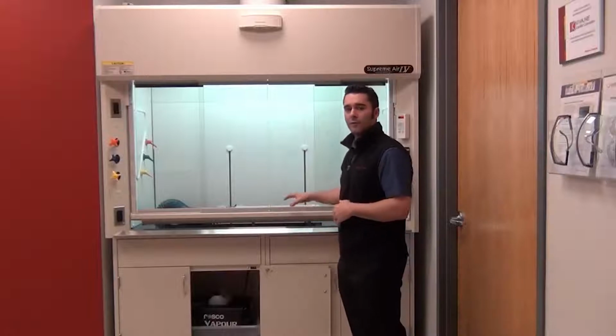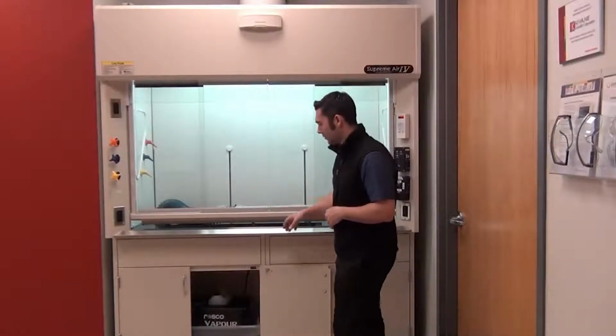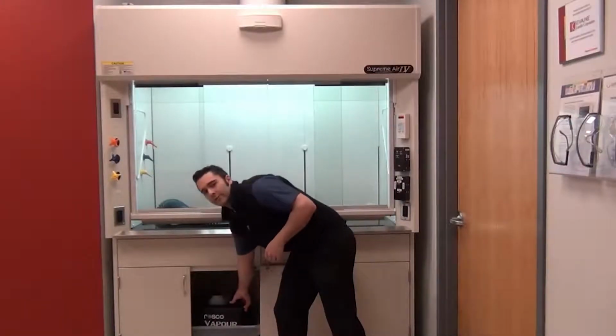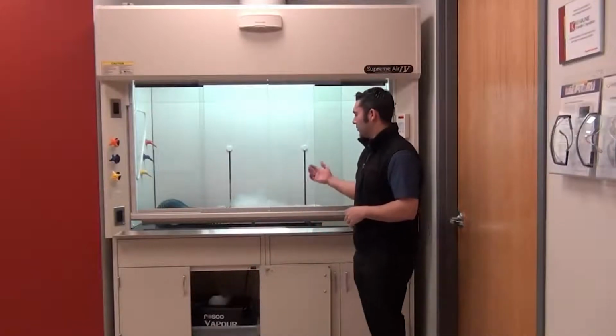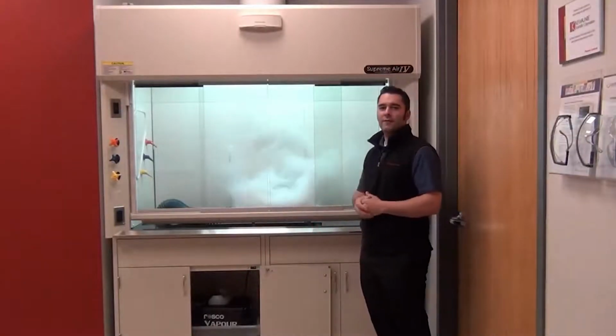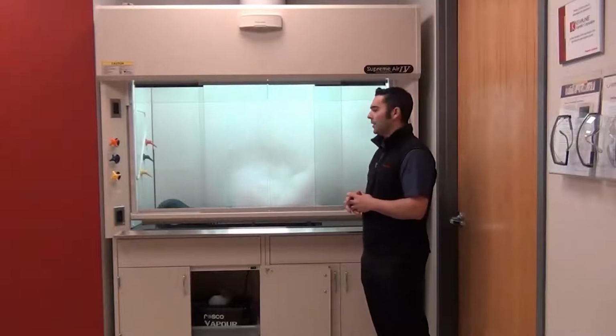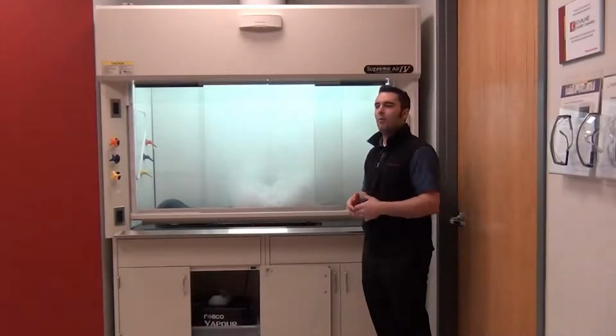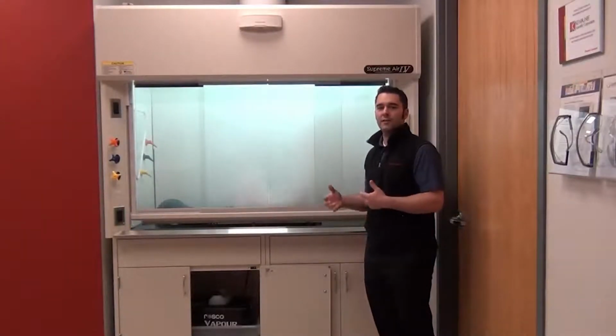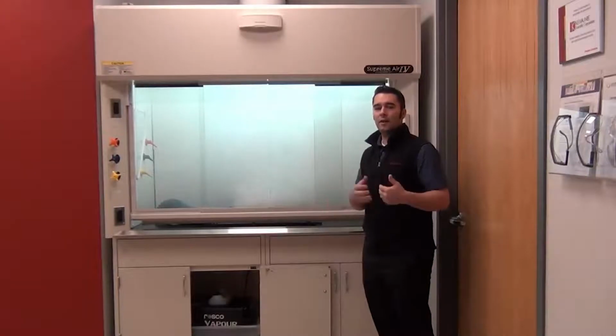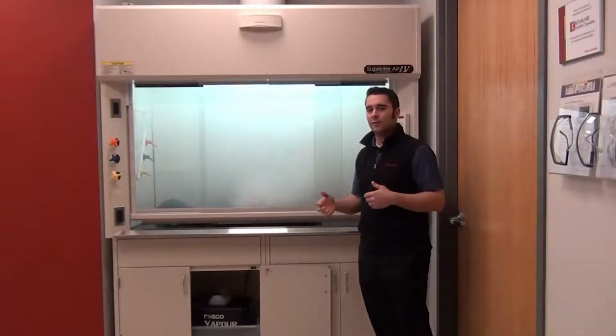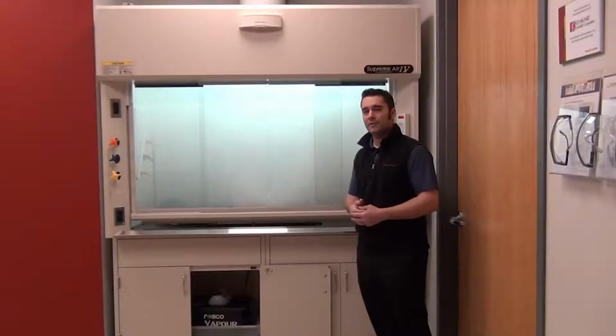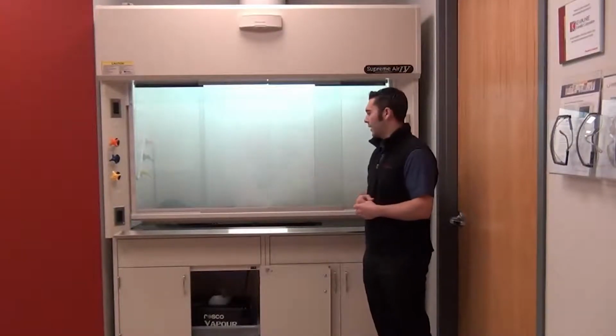So I'm going to turn on a smoke machine that we have in here. We use theatrical smoke to simulate chemicals inside of the fume hood. As you can see, this is safe, non-toxic smoke. But we like to use this again just to show how the speed of response will react inside of a 1 second valve, and I can also show you what a 3 second speed of response, which is kind of the industry accepted standard, or a 6 second speed of response in this same fume hood would react.